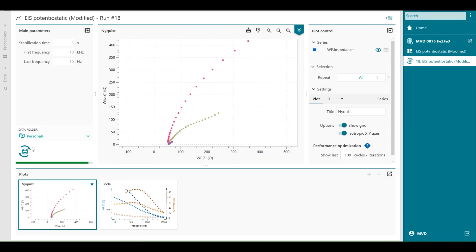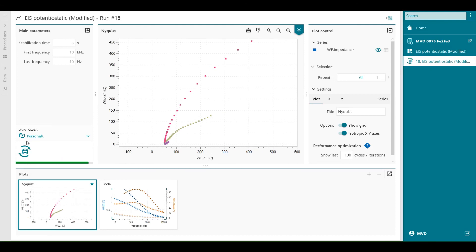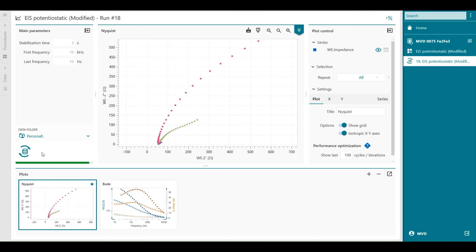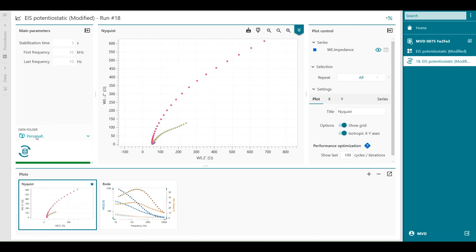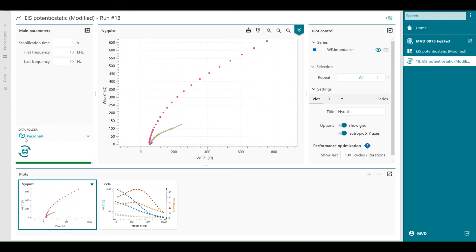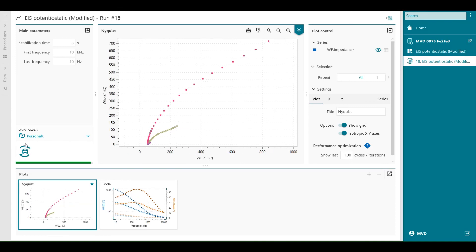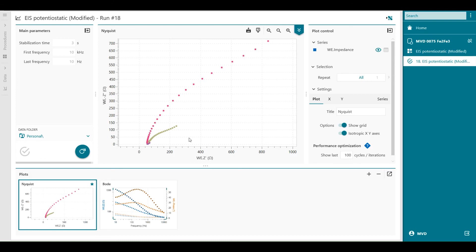The measurement is finished. The data is saved to your personal data folder. So when this is finished, it will automatically save all the data. So as you can see here in the data, there's an influence of the AC perturbation and the DC voltage on your impedance measurement.